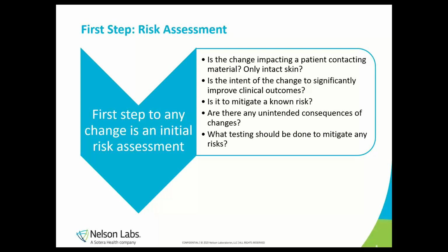I'll give you one example. We had a customer a couple of years ago change the packaging label on their device. Actually, it was inside the sterile barrier. It was like a pamphlet or something like that. They were changing the color they used in that pamphlet. And when the customer went through the risk assessment, they said it's not patient contacting, so therefore no change evaluation is needed.